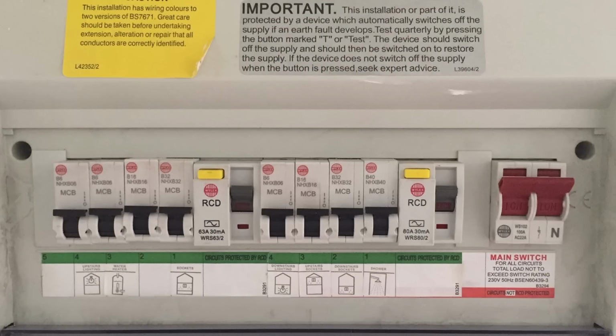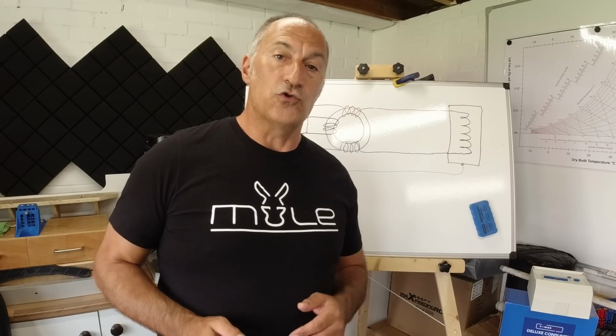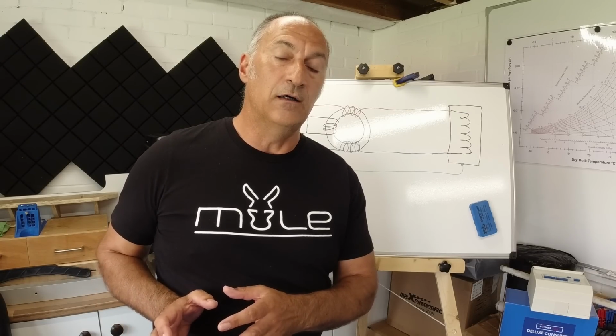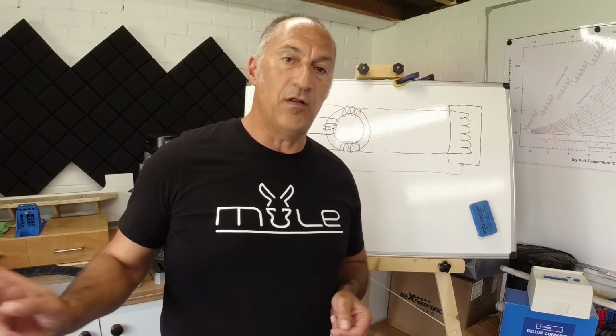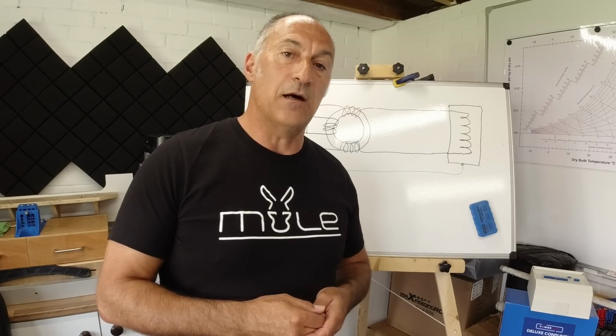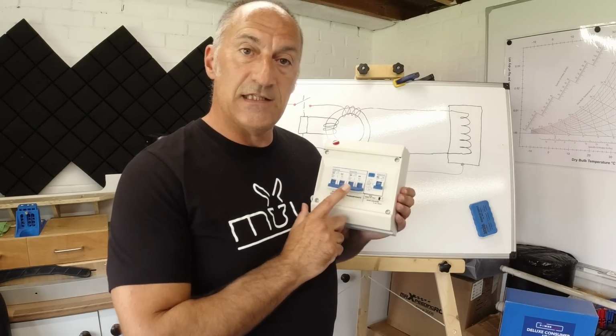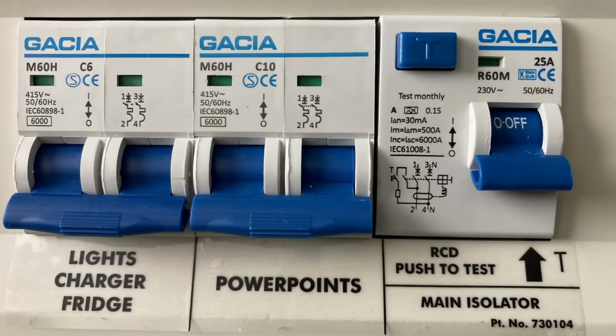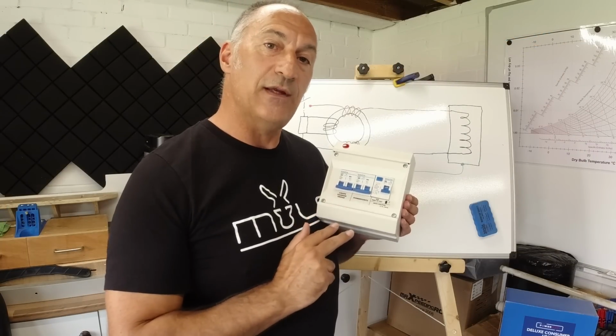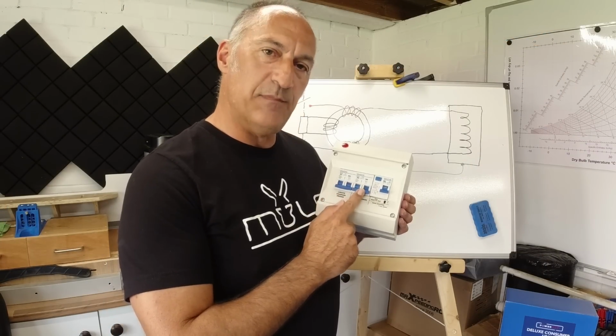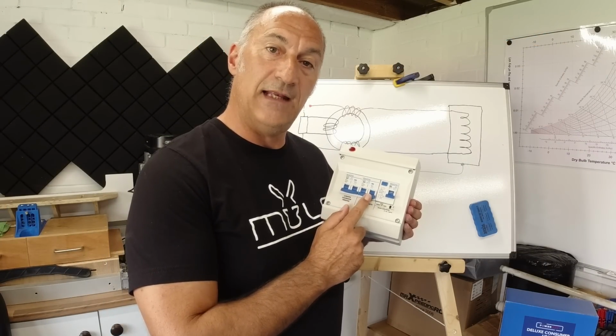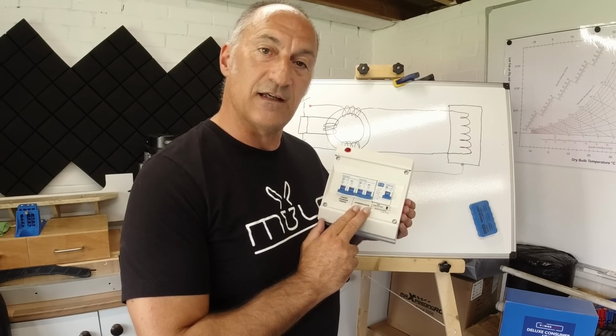Traditionally, the MCBs that you'll find in the consumer unit in your house will just be single pole. They'll only normally break the line conductor, and the neutrals will all be common together on a neutral bar. But for our campervan, and in order to comply with that regulation, ours are going to need to be double pole. So as you can see in this consumer unit, we've got the double pole RCD first, and then next to that we've got two double pole MCBs. So we can have two outgoing circuits here, and each of these MCBs will be capable of breaking the line and the neutral for its respective circuit.